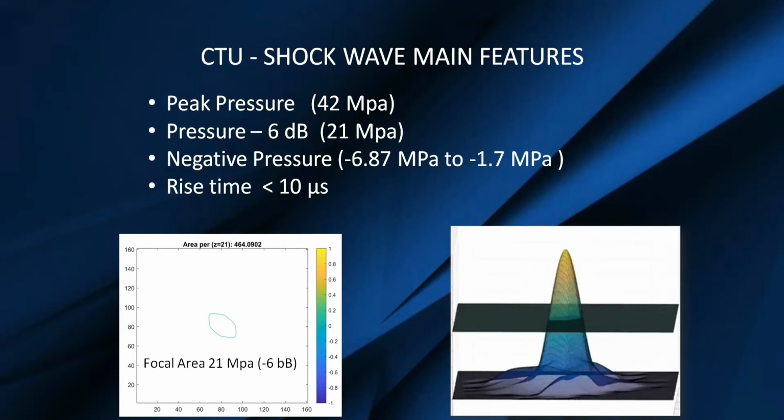But one of the more characteristic aspects is the negative pressure, which is not so high in mean values compared to the other technologies. We can see that the negative pressure is at minimum 1.7 MPa. It means, and I will explain this concept better, that the pain or the possible damage to the cells is minimal, also with higher intensity of the energy.